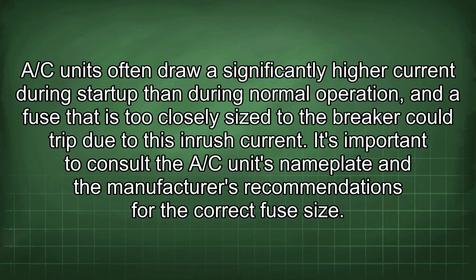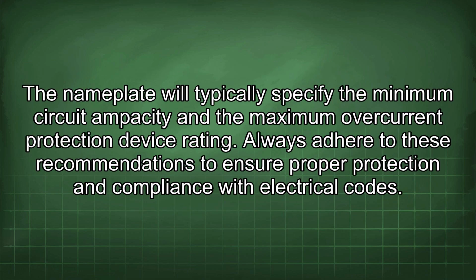It's important to consult the A/C unit's nameplate and the manufacturer's recommendations for the correct fuse size. The nameplate will typically specify the minimum circuit ampacity and the maximum overcurrent protection device rating. Always adhere to these recommendations to ensure proper protection and compliance with electrical codes.